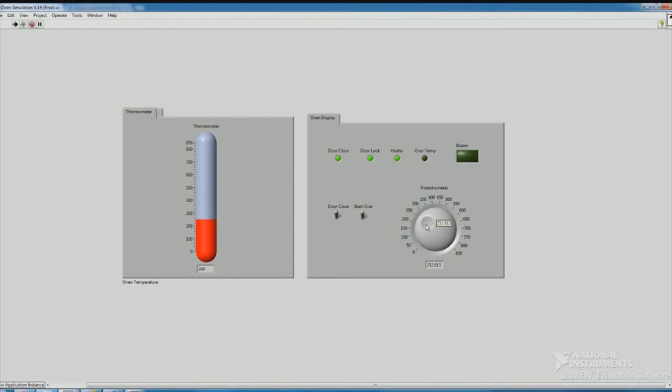Now we will show you the alarm mode. We set a temperature value higher than 800 degrees and we wait until the measured temperature is over 800. Once the program registers this value, the buzzer will start and the LED will be on. A message will notify this failure, and as you can see, the heater is shut down for safety reasons. The door must be kept locked due to the high temperature inside. As you can see, the temperature is decreasing. Once the temperature is below 100 degrees, the door is unlocked.